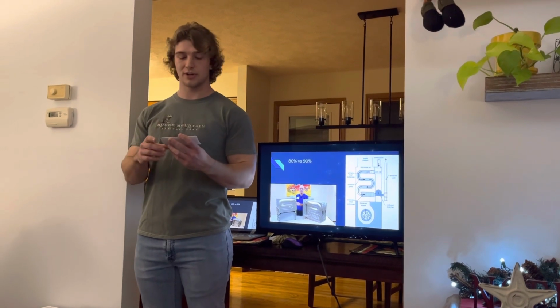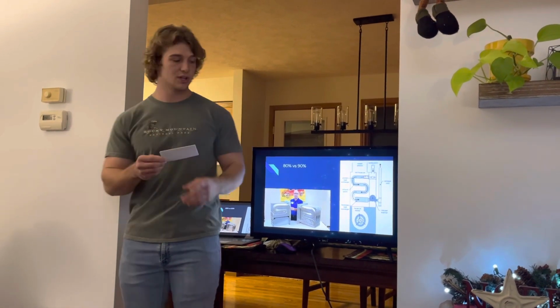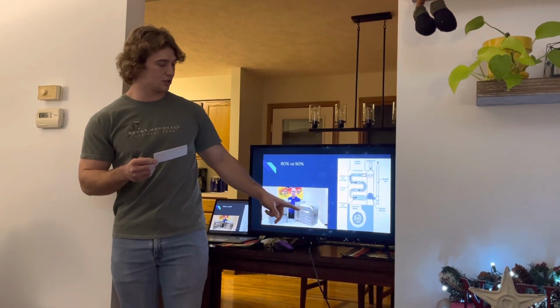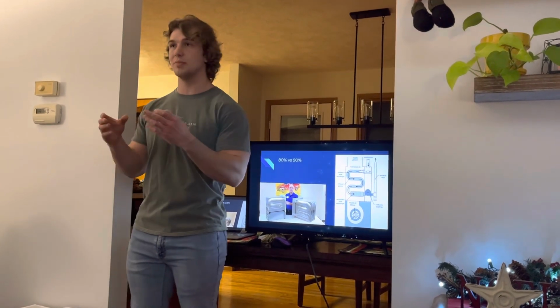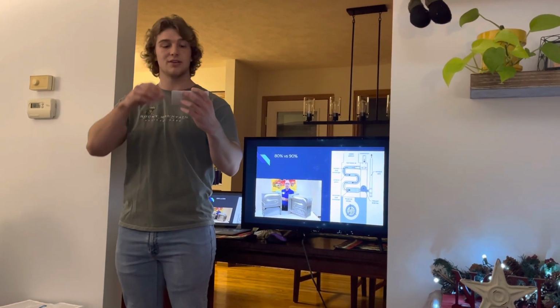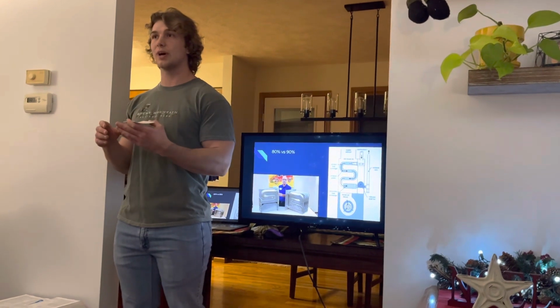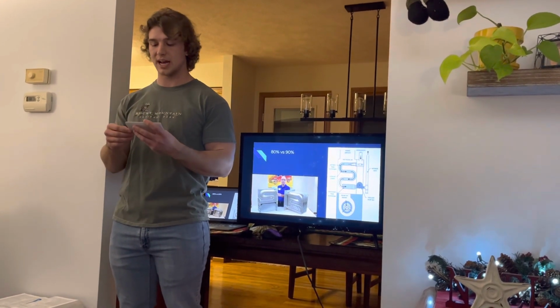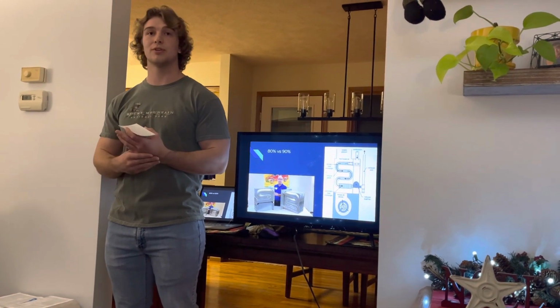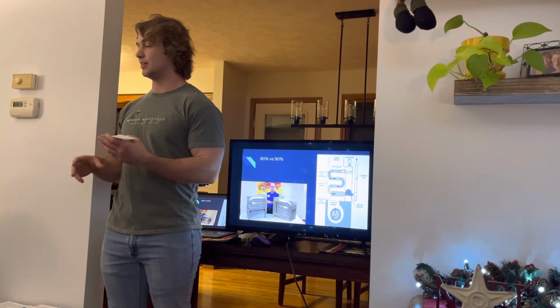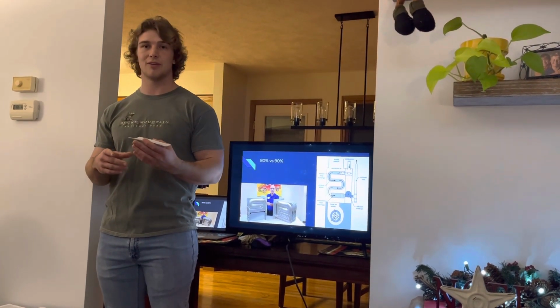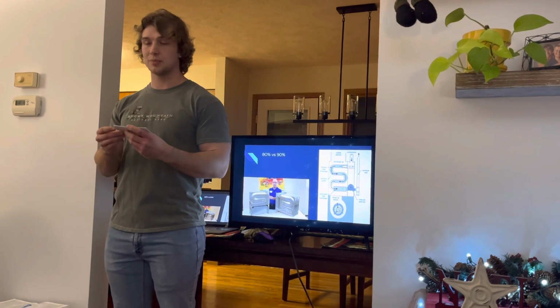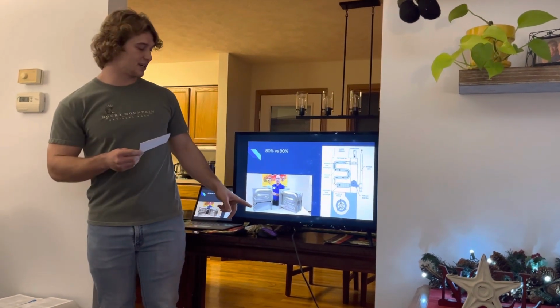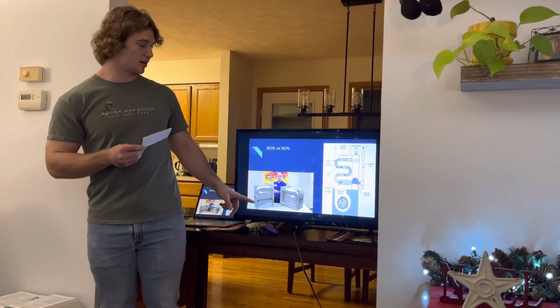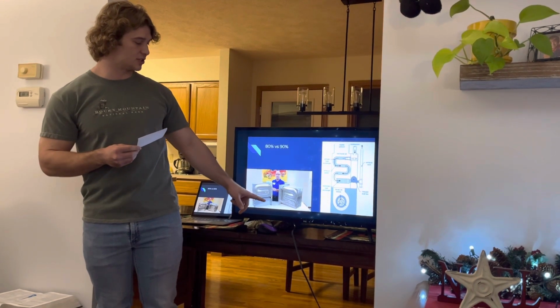An 80% furnace is a standard gas furnace with a single heat exchanger, shown right here, that uses metal flue piping to vent your exhaust outside, and it burns indoor air alongside combustion with your gas. Now, a 90% furnace is more efficient than an 80, and there's a few technology differences that allow for this. Now, a 90% furnace utilizes a secondary heat exchanger shown down here. Here's your first heat exchanger and here's your secondary.